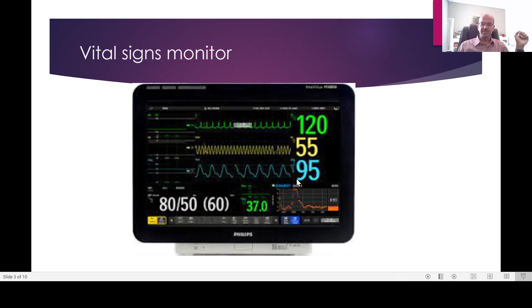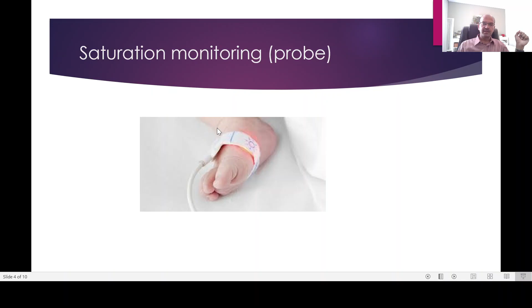This is the pulse oximeter probe which you find on the hands or feet of the baby, and through which the saturation which I indicated here is measured. It emits a red light, and by comparing the proportion of red and infrared light, it gives us a percentage of hemoglobin that's saturated with oxygen. So it's an indication of oxygenation in the baby. The nurses do re-site it every 4 to 6 hours as per the unit policy.